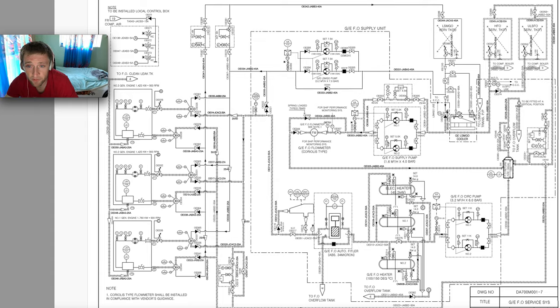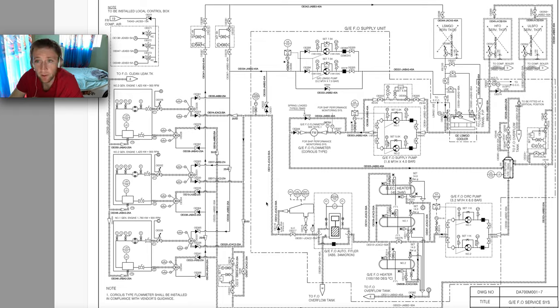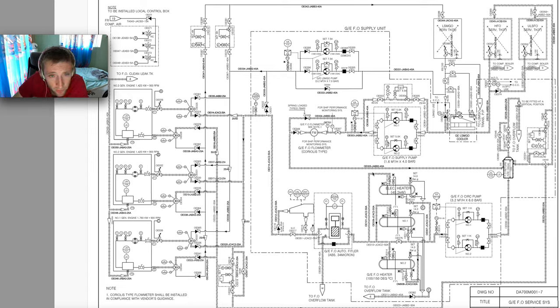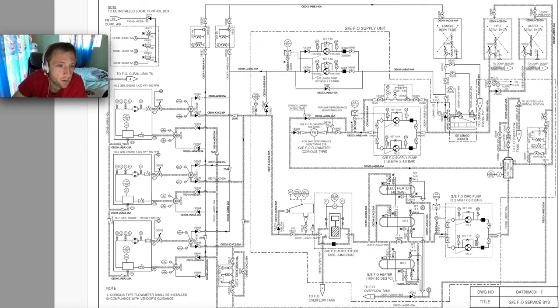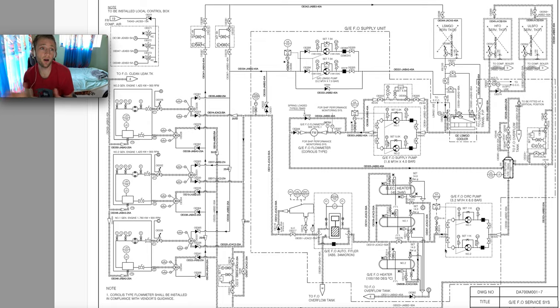Let's make a review of the system: we have the suction from here on a separate line and we send our diesel here, we make the changeover, then the fuel will be returned back here. After this, this valve will also be changed and you will have the indication. You can check locally, close the fuel outlet valves, so you will be sure your engine is not running on fuel anymore — fully isolated and running on diesel. After that, you can give the load to your engine and deload another engine and start the procedure of changeover again. You can also give this ultra low sulfur MGO to the fuel line and wait for the flushing to finish before closing.